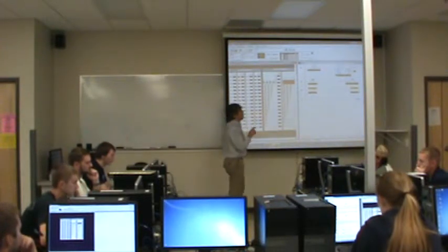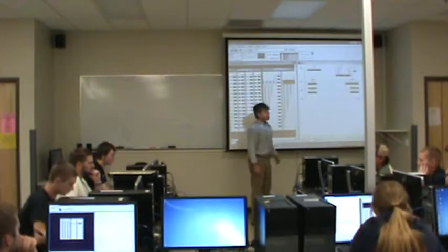Well, it turns out the way that Allen Bradley does it is it will continue to count, but nothing really changes. Because really the comparison is if the accumulated value is greater than or equal to the preset, then the done bit is on. Right now our accumulated value is 16, preset is 10, and the counter is done because the accumulated value is greater than or equal to preset. So it's pretty straightforward. It's easy to use once you understand what the bits are for.